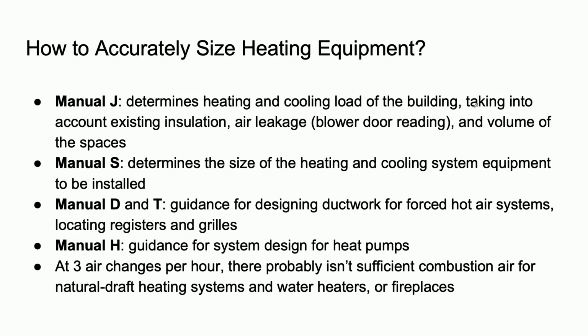All right. So how do you size heat pumps? This is something that Scott talked about. I had mentioned this before. Manual J heat load calculation. This isn't just for heat pumps. This is for putting in any new heating system. The heating contractor should do what's called a Manual J heat load calculation. So this is basically taking into account the existing insulation in the building, what's in the walls, what's up in the attic, in the basement, also how much air leakage there is in the house, which the only way you can test is with a blower door, which we did today. You cannot do a proper Manual J heat load calculation unless you know what the air leakage is in the house.